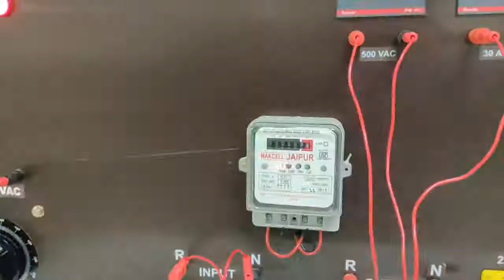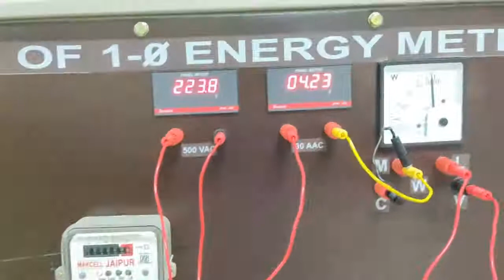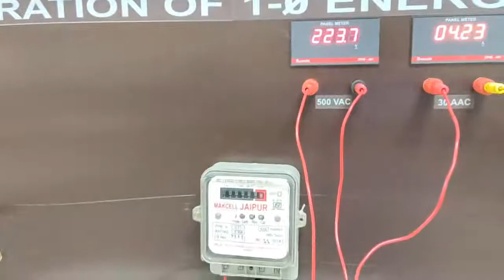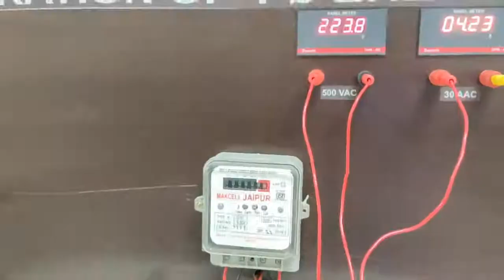This is how the number of revolutions is calculated using the energy meter, stopwatch, voltmeter, and ammeter, and we have to calculate the meter constant and find the error in the meter constant of that energy meter. So this is the calibration of the energy meter.